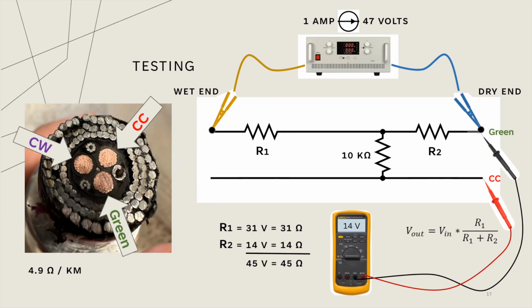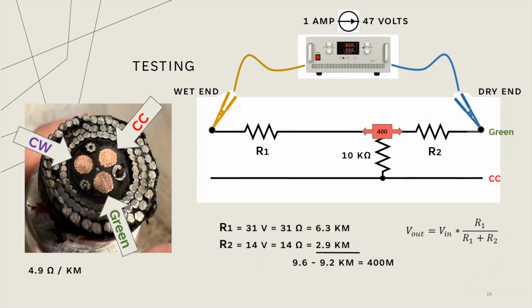So right away, with our simplified math here, you can tell that the fault was about 2/3 into the cable reel. It was pretty deep, not an ideal situation. And we had some error there, right? The 31 plus 14 adds to 45. That's not quite 47. So we had a 400-meter range where we knew the fault was. And as it turned out, there were actually two faults. I didn't show the K-tube here, but one of the conductors was faulted to the K-tube in a different place than the other was.